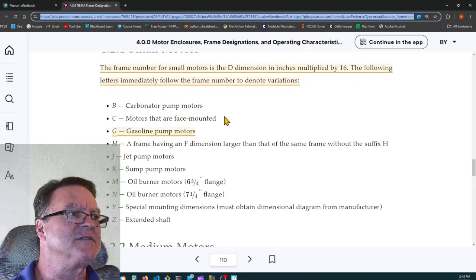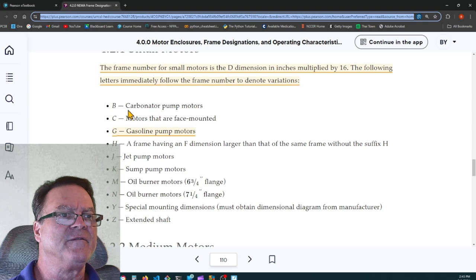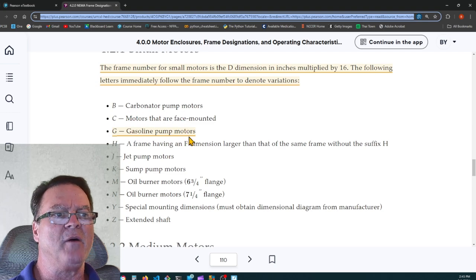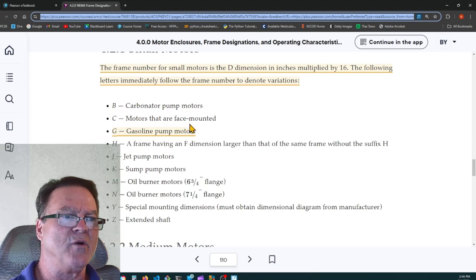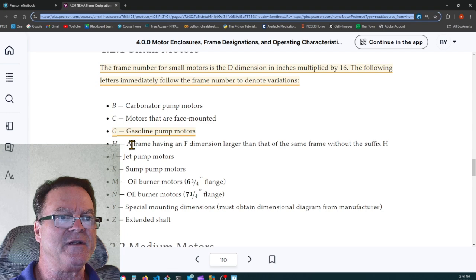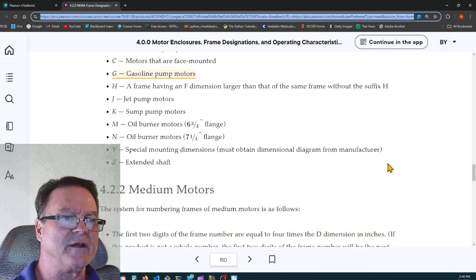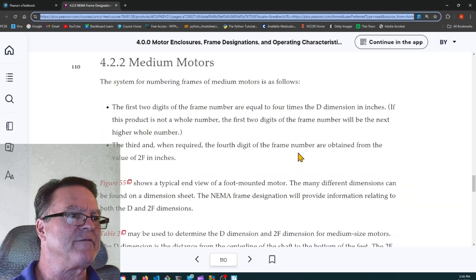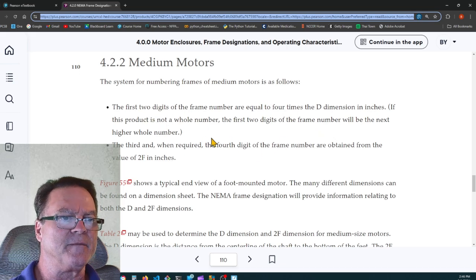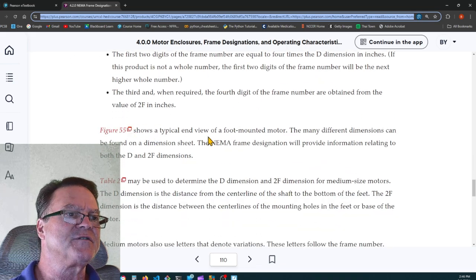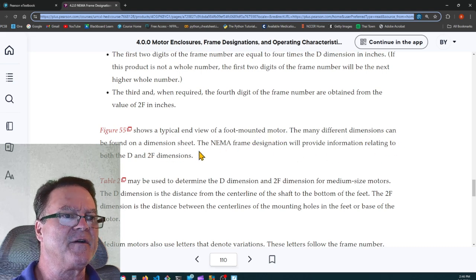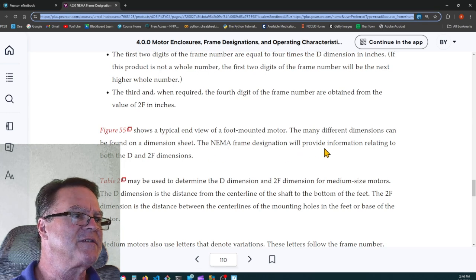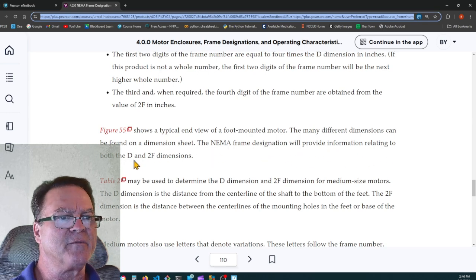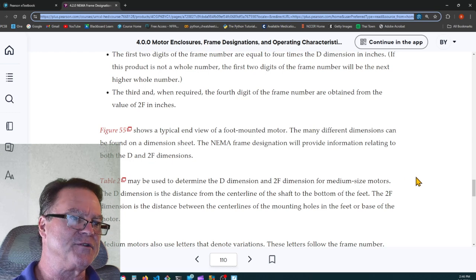And they have these variations. G is a gasoline pump motor. So carbonator pump motors, B, motors that are face mounted, are C. I have G highlighted there. But medium frame, here's where we have that D and the 2F dimension. This figure 55 shows a typical end view of a foot-mounted motor. Many different dimensions can be found on the dimension sheet. The NEMA frame designation will provide information related to both the D dimension and the 2F dimension.